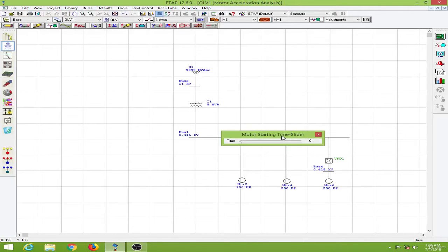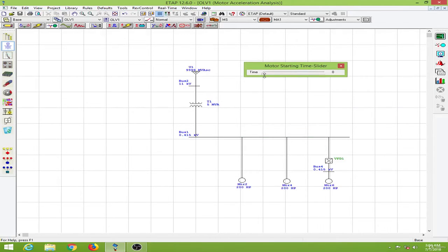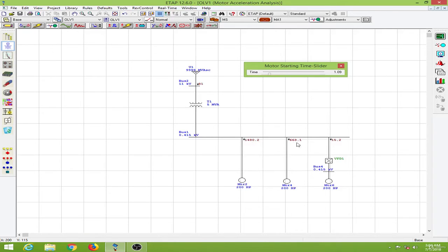Let us close this. The motor time slider appears, so let me go to the 1-second mark. We can now see the inrush current for various starters. Motor 2 has no starter, so this is its inrush current. Motor 4 with the auto transformer starter has 663 amps of starting current, and for the V/f drive this is the starting current, which is much lower, varying gradually as the starting period progresses.